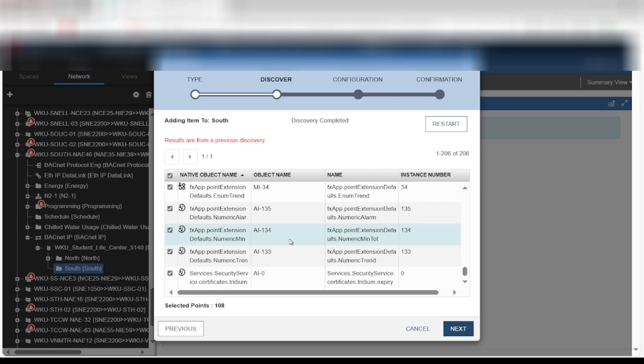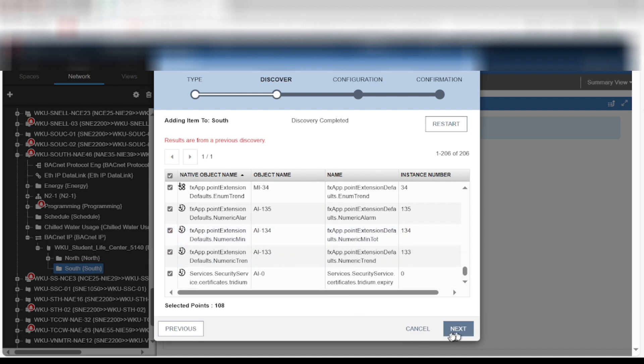It will select the remaining points and bring them into the system. It's not very difficult — you just have to follow the right steps. One thing to mention: when you pull these points in, depending on the flavor of Tridium you're using, some of those points when you try to command them may not be commandable. This is one of the unfortunate realities about making these systems work together — there can be combinations that are not as friendly as others. If you have any questions, leave them down below — hope you liked the video, thanks for watching.